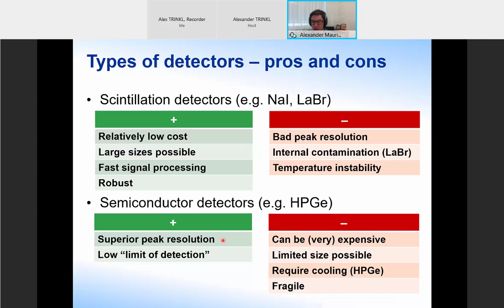They require cooling, especially high purity germanium, and they are relatively fragile. So if you look at just the number of pros and cons, you might think, oh, this high purity germanium doesn't have so many advantages. But actually this peak resolution is so important, and we will see now why the high purity germanium detector is really considered the gold standard of gamma ray spectrometry measurements. In order to look at resolution, we need to define one concept, the full width at half maximum. This is how you measure the resolution, or sharpness, of the peak.